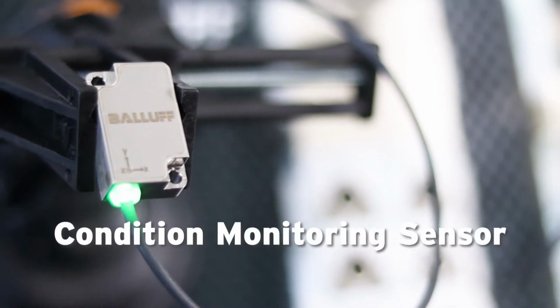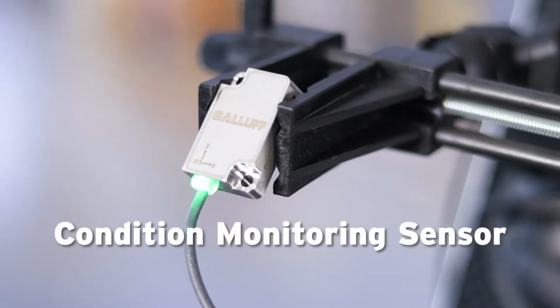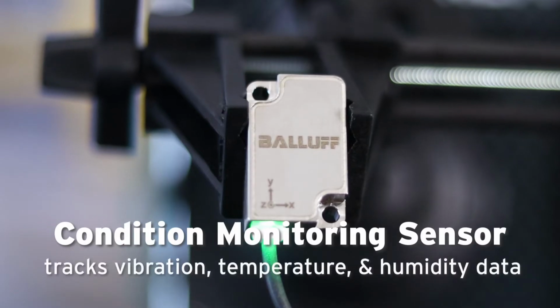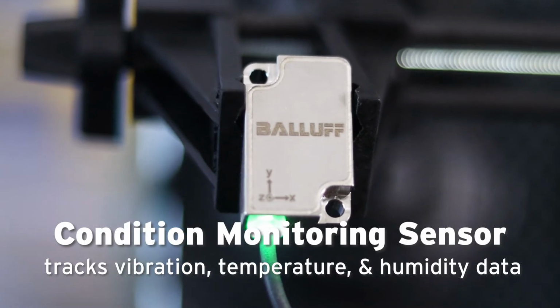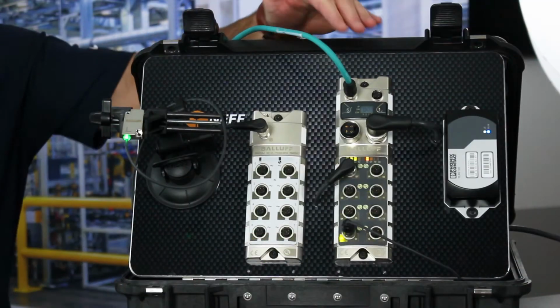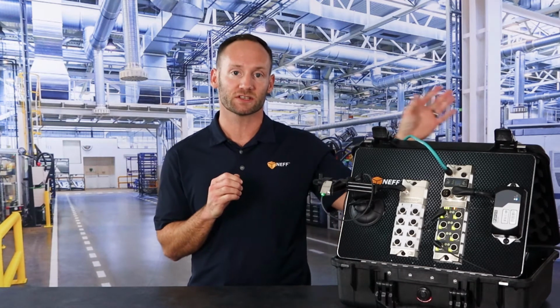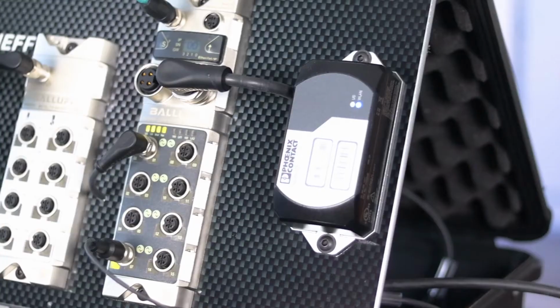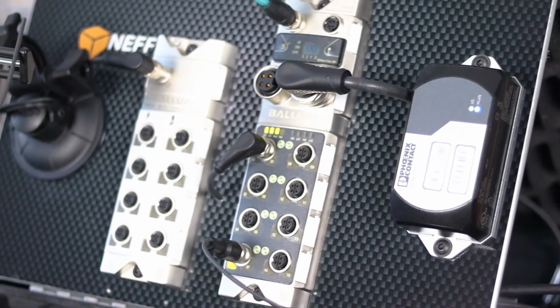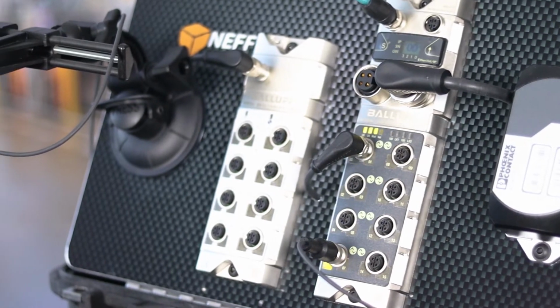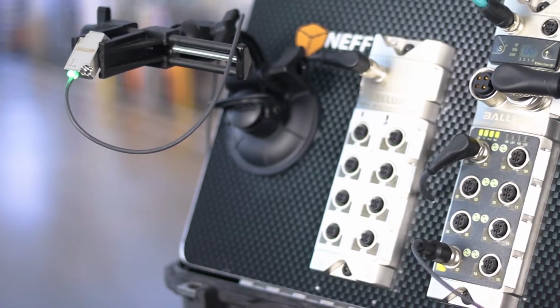The BCM condition monitoring sensor from Balluff provides vibration, temperature, and humidity data for analysis over IO-Link. When paired with the Balluff IO-Link master block, we can send the data that's relevant to the machine operation to the PLC via Ethernet IP, Profinet, or other industrial protocol, then send a parallel path with JSON data up to the SCADA level. For today's demo, we're using Ignition. However, this could be Aveva, Wonderware, OSIsoft PI.